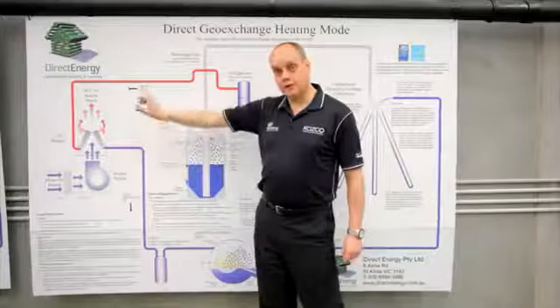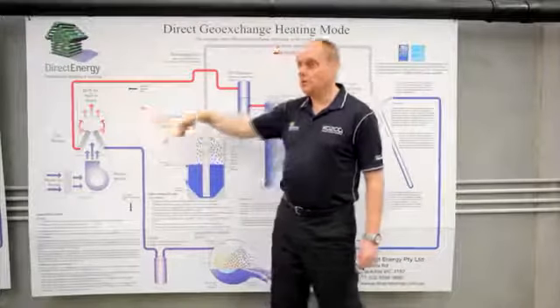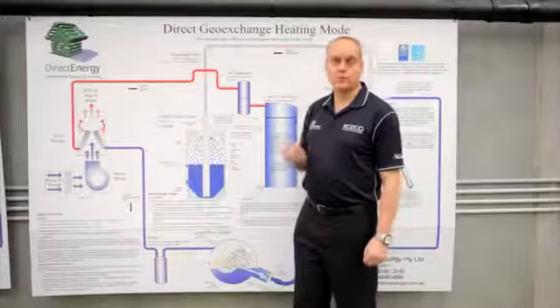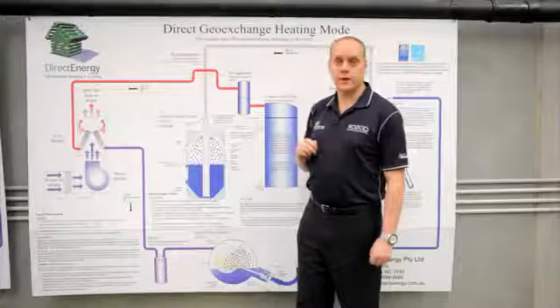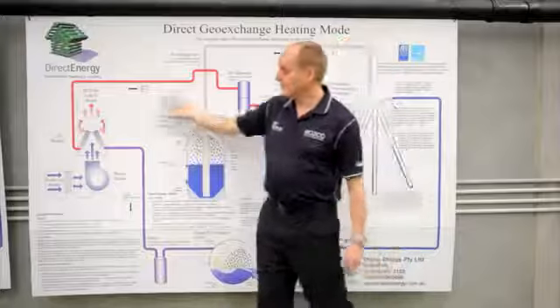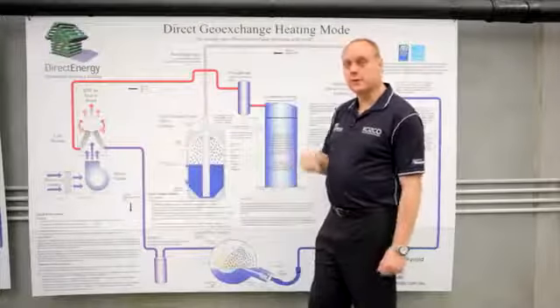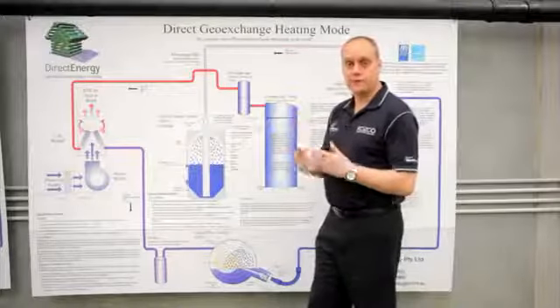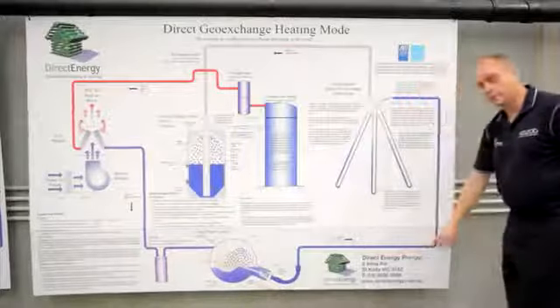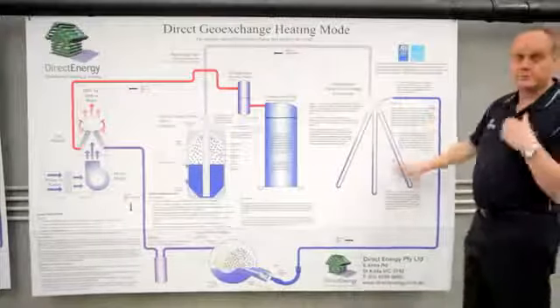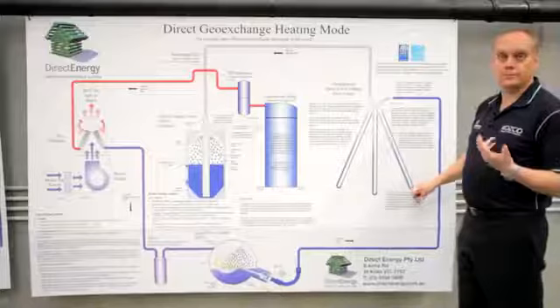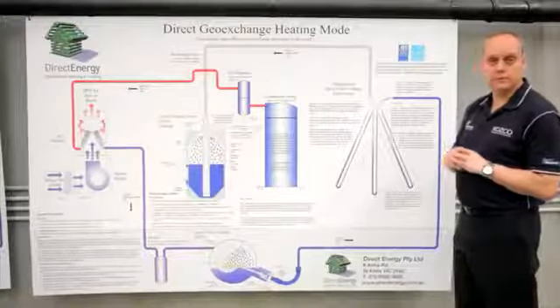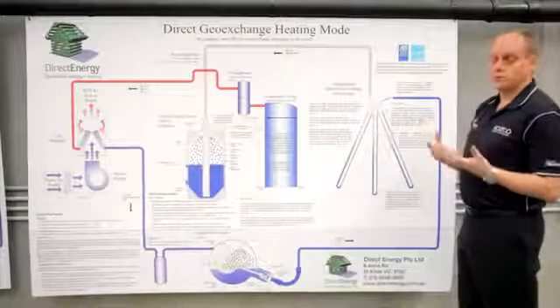in this case, a fan coil unit for heating air in a building, or, in the case of producing potable water or water for hydronic floors or radiant wall panels or swimming pool heating, to go to a water-based heat exchanger to transfer that thermal energy into water.